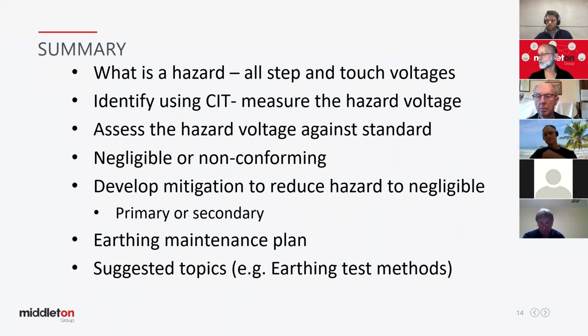Yeah, it's neutral earth resistors. The downside in using neutral earth resistors, it sounds like there might be a few trade-offs that you might mention. Correct, Chris. There is, yeah. If you think about it, if you're going to put a resistance between your star point and the ground, during a fault, your star point will raise in voltage, pushing current through a resistor. So that point's going to raise, and that's going to raise your line voltages as well. So you need to consider insulation levels of your phase conductors as well. Quite typically, it might mean you're adding another disc insulator to your overhead lines or something. But good question, Chris, you're right. Introducing an NER, we do have other considerations to make in terms of the insulation. Thanks for your question, Chris.